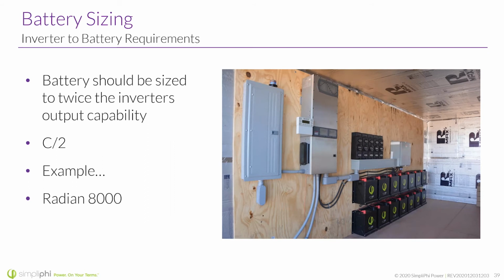So please just follow that sizing - it's in all our installation manuals, warranty documents, and integration guides, and you'll see the math there. It's very straightforward. We don't have a maximum; you can put as many batteries as you want on a smaller inverter, but we do have a minimum, so keep that in mind. Charge controllers don't have a minimum as much, since we can program those to limit the charge, so we really just have to watch out for the inverter and hit that minimum number. Again, if you have the AmpliPHI battery with the SolArk communicating, we don't have that requirement.